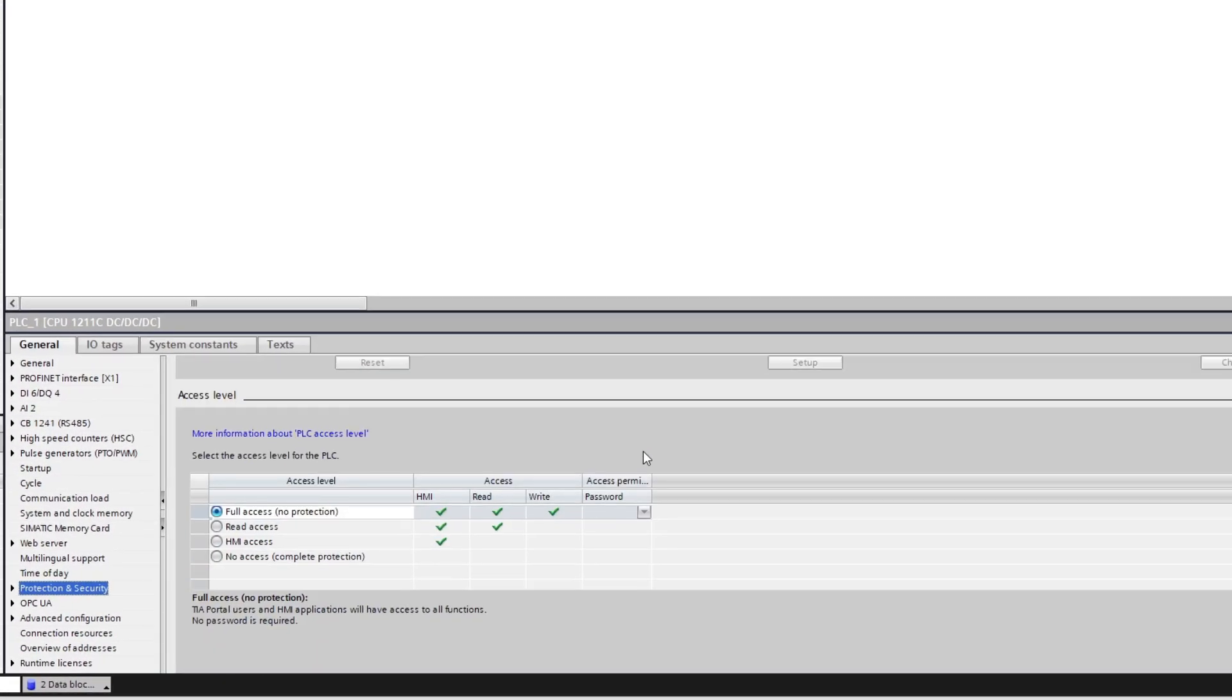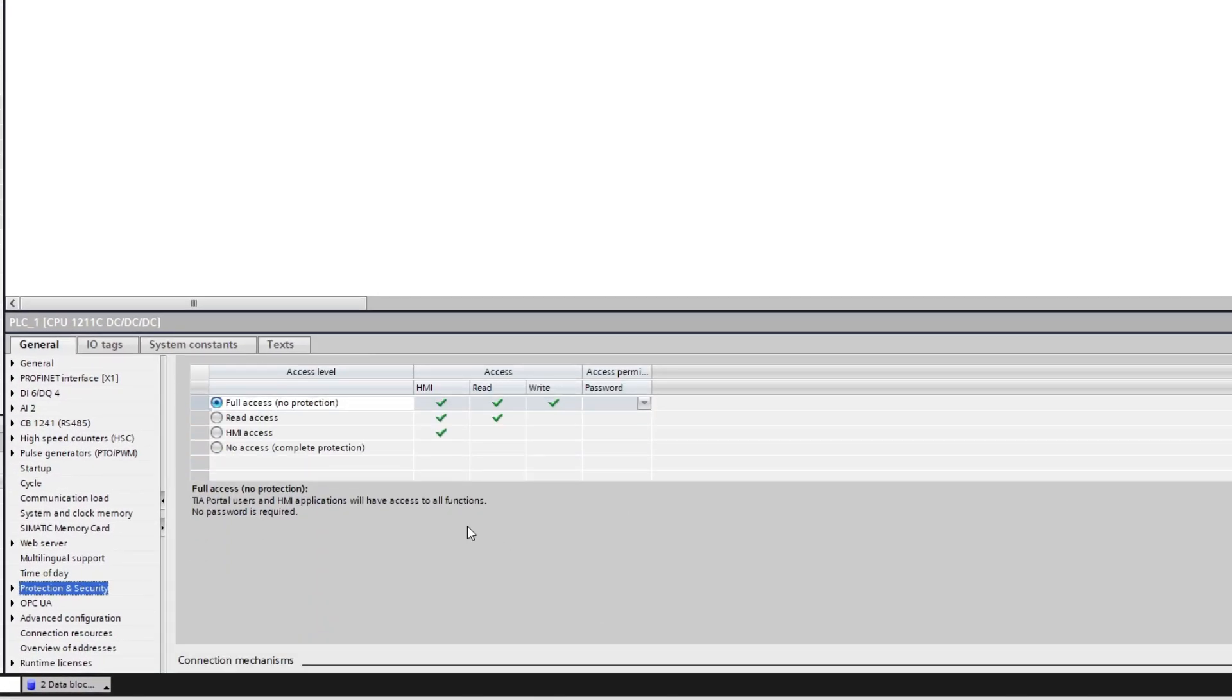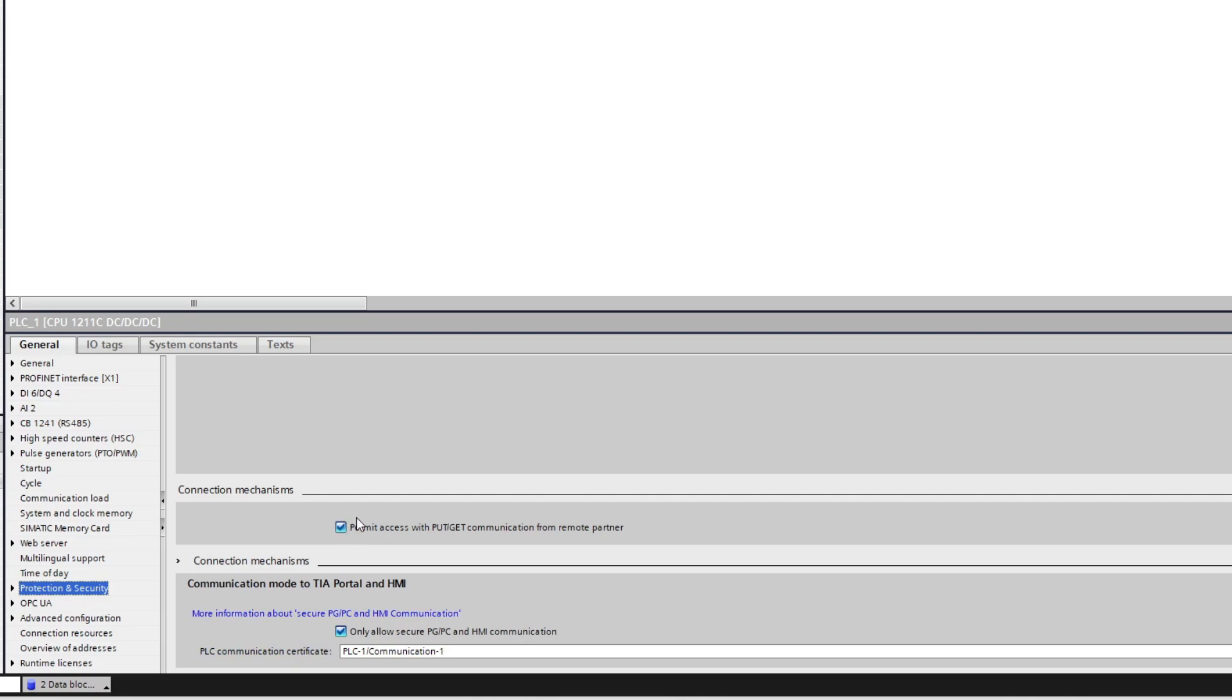Next we want to double click on our PLC and go to the Protection and Security tab. If we scroll down a bit in this setting we will find a box that we need to make sure is checked that says permit access with put get communication from remote partner.